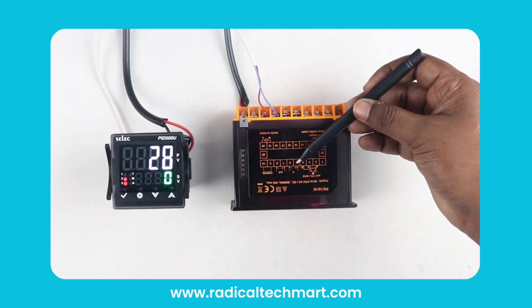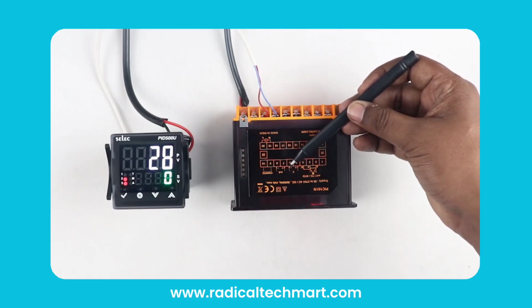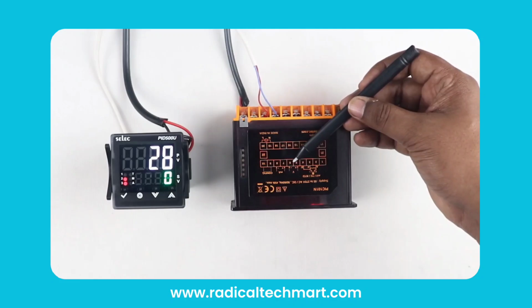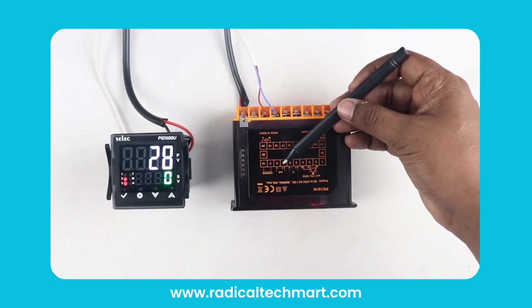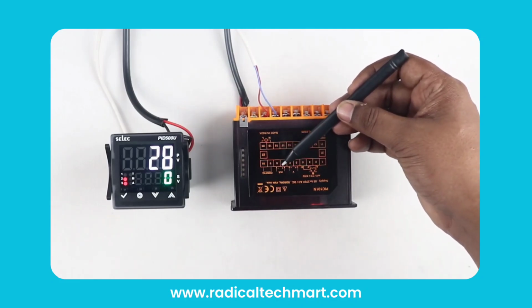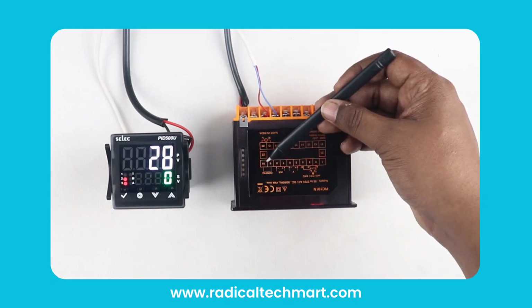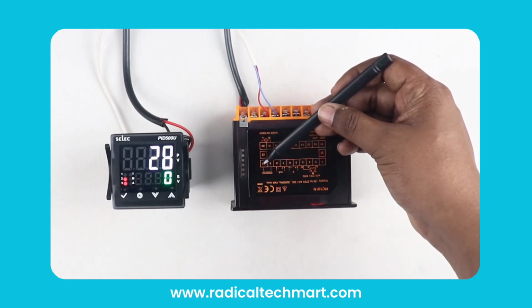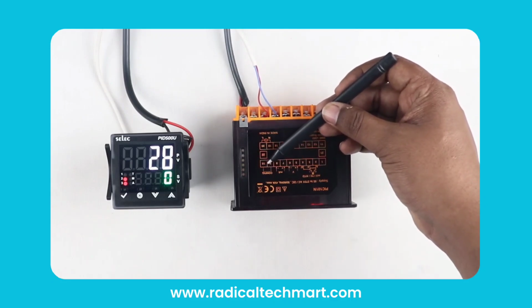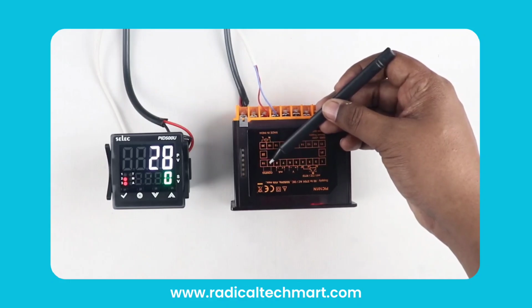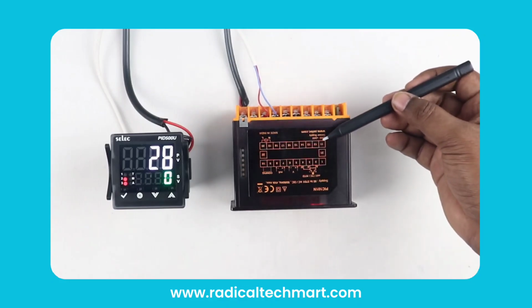For voltage input, use terminals 5 and 6, where 5 is positive, plus symbol, and 6 is negative, minus symbol. Terminals 7 and 8 are for your milliampere input, with 7 being positive, plus symbol, and 8 being negative, minus symbol. For programming, terminals 9 and 10 are used.